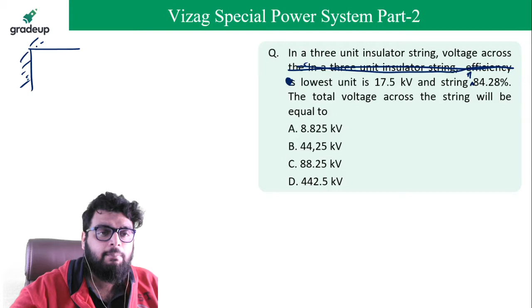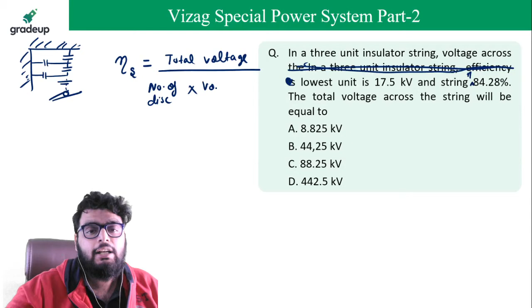Okay, now what is the formula of string efficiency? The formula of string efficiency is total voltage divided by number of discs multiplied by voltage across the last disc, voltage across the lowest disc, or you can say the last disc also, anything you can say. Okay, now what is the string efficiency? It is 84.28 percent, changing into a decimal, 0.8428. Total voltage I need to find out. Number of discs is 3. Voltage across the lowest is 17.5 kV.